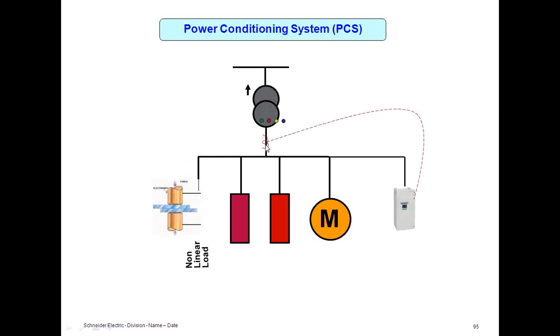So we have a sensing at the main transformer secondary side that will sense the complete load on the transformer, including welding loads and harmonic drives, UPS, etc. So the one machine can do the job of all the fault issues, which includes harmonics, voltage fluctuations, and reactive power variations, and so on and so forth. So this is cancelling out here.